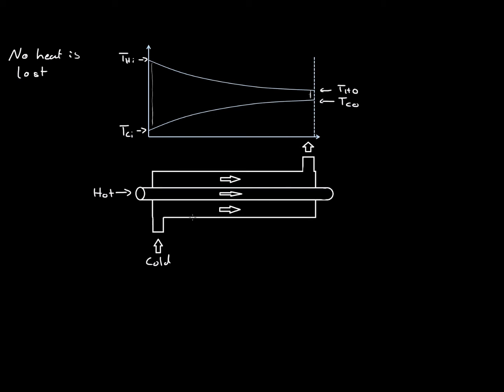So how can we calculate the heat loss from the hot water? It is Q̇ = ṁ_H · C_PH · (T_H,in − T_H,out). The same is true for the cold water: Q̇ = ṁ_C · C_PC · (T_C,out − T_C,in). Note the order is reversed so that Q has the same positive value for both, and these values are equal.